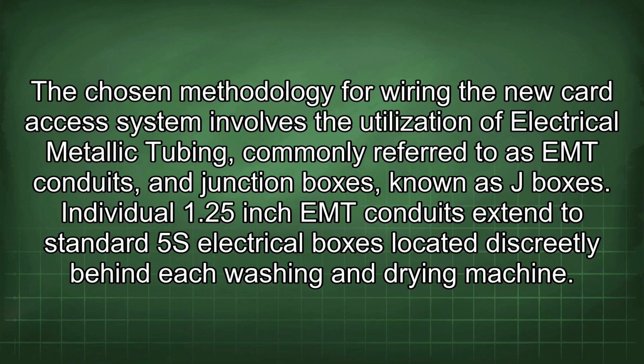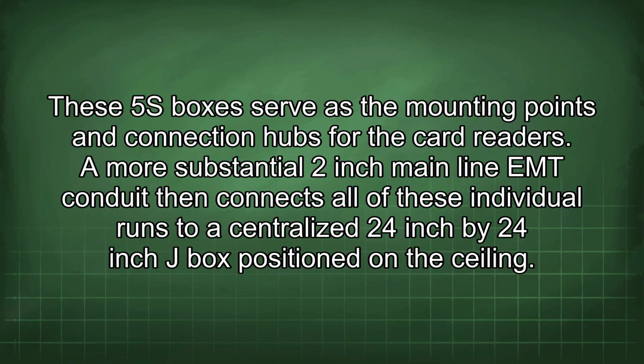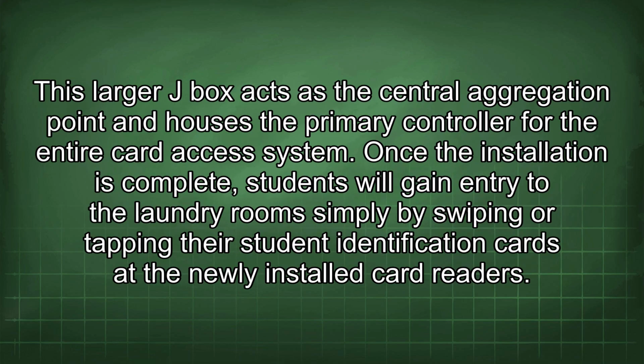Individual 1.25-inch EMT conduits extend to standard 5S electrical boxes located discreetly behind each washing and drying machine. These 5S boxes serve as the mounting points and connection hubs for the card readers. A more substantial 2-inch mainline EMT conduit then connects all of these individual runs to a centralized 24-inch by 24-inch J-box positioned in the ceiling. This larger J-box acts as the central aggregation point and houses the primary controller for the entire card access system.